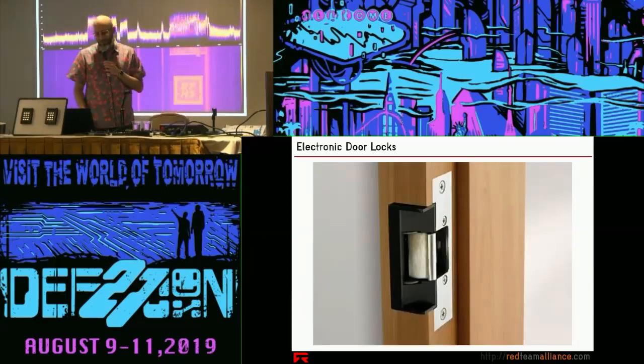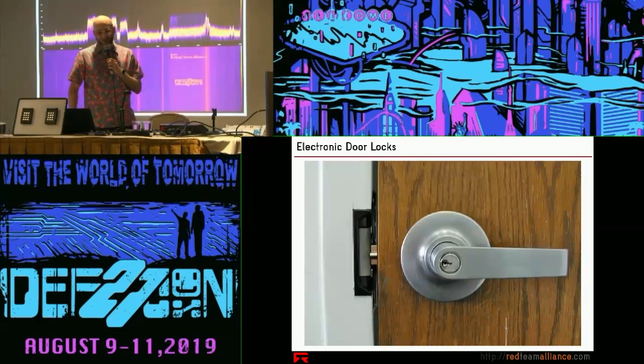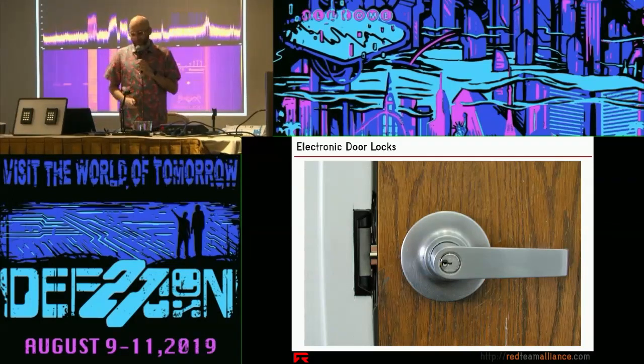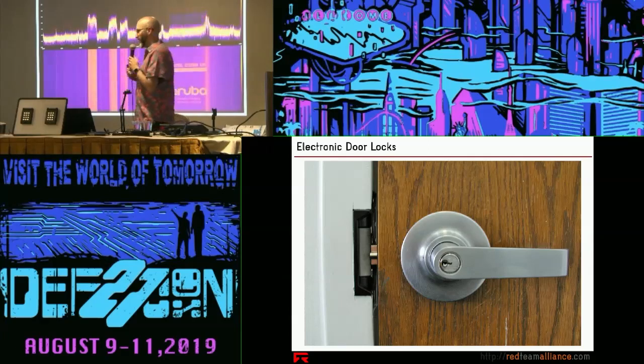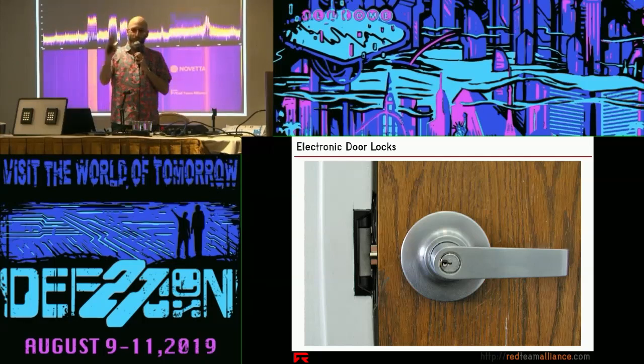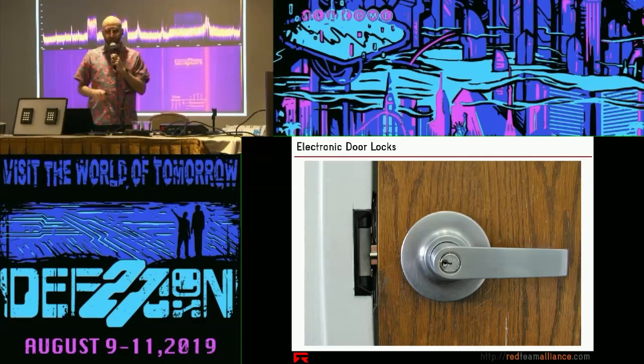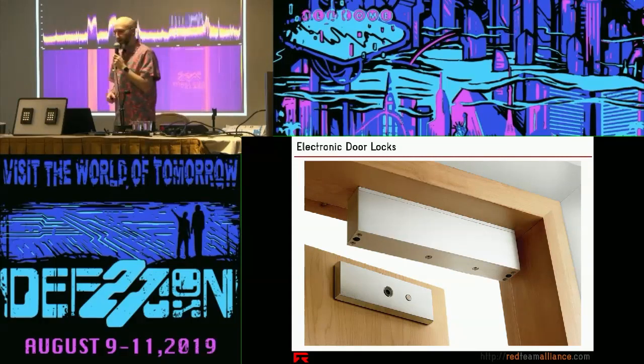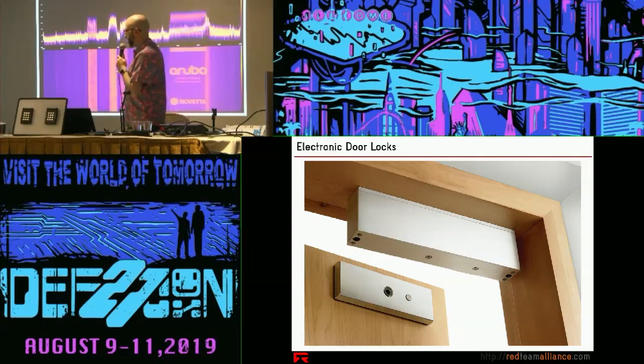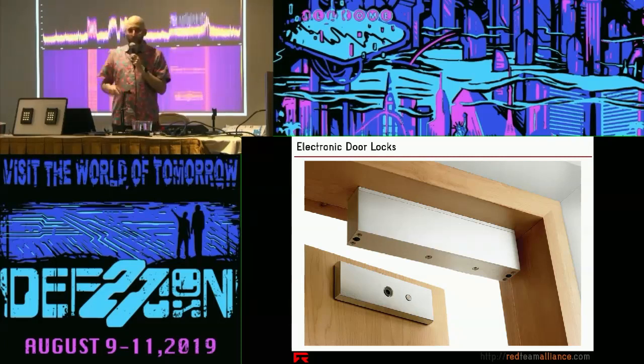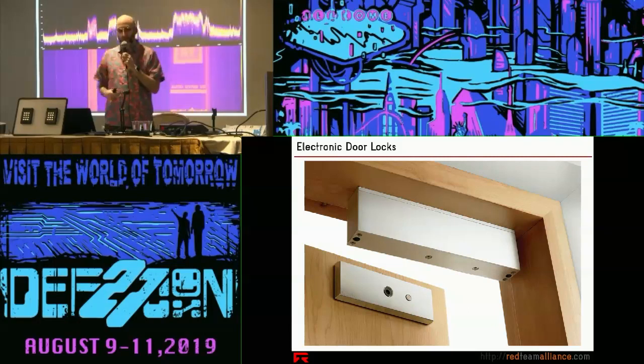First you have the electrified strike. This takes the place of the existing strike plate, and there's a little solenoid inside. Whenever you apply a voltage to it, it allows the strike to swivel out of the way so you can just pull the door open without even turning the handle. Second is the magnetic lock — two-piece construction with an electromagnet and a steel plate. When you apply power, they stick together very well.